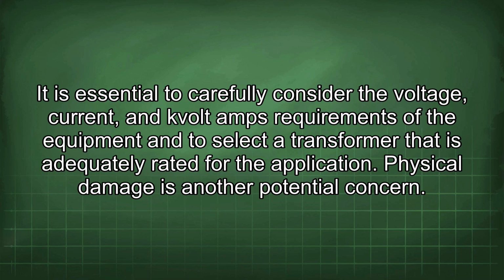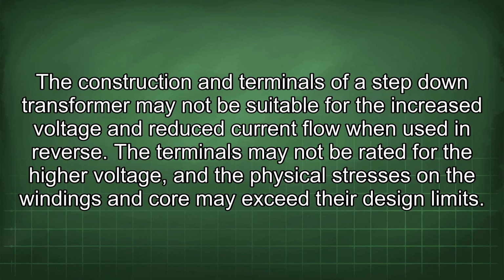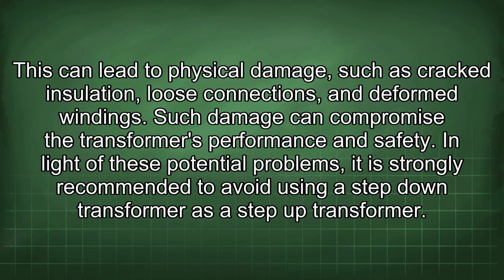Physical damage is another potential concern. The construction and terminals of a step-down transformer may not be suitable for the increased voltage and reduced current flow when used in reverse. The terminals may not be rated for the higher voltage, and the physical stresses on the windings and core may exceed their design limits. This can lead to physical damage, such as cracked insulation, loose connections, and deformed windings. Such damage can compromise the transformer's performance and safety.